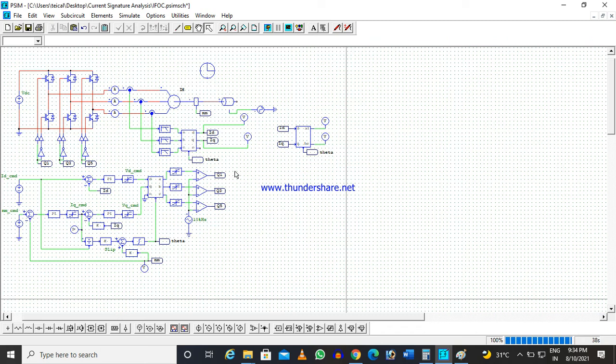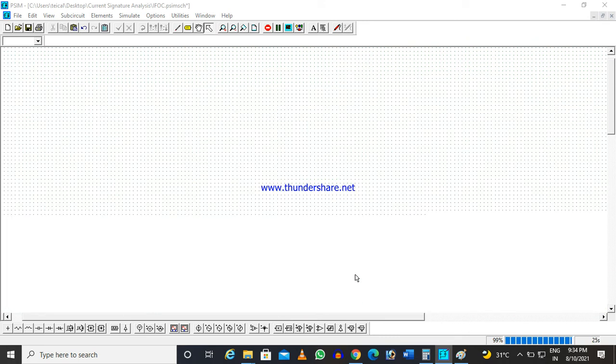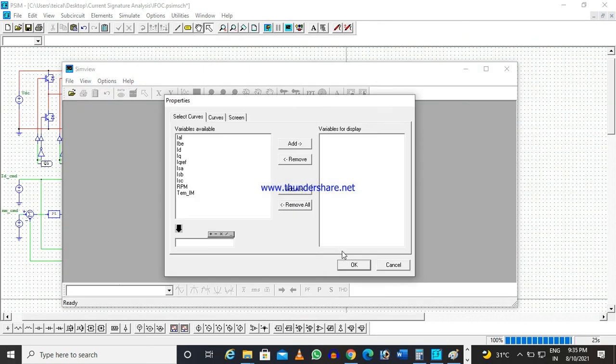Now let us see what is my torque producing component now. Actually I don't have direct access to the driven equipment, but I have access to the current in my control room. So I am taking the current signature of the torque producing component, not the direct line current or phase current. As I told from that fan example, it is very difficult to predict that component. So this is my quadrature component.